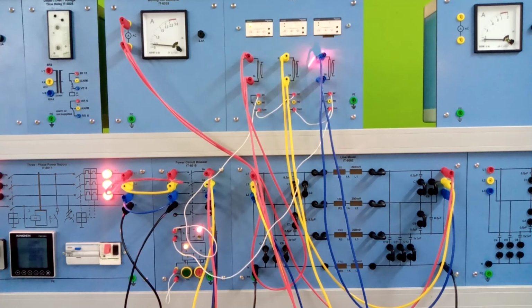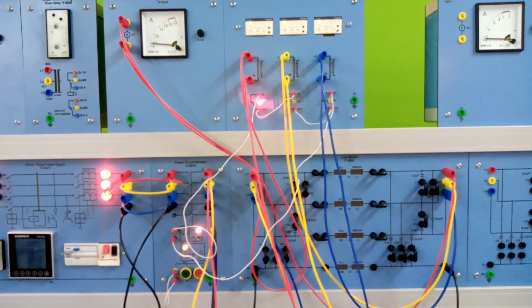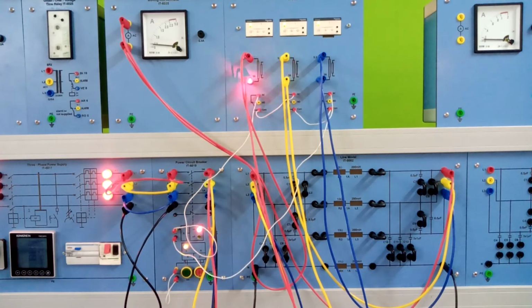We have reset them again and they are initializing, and the third portion is about short circuiting with the ground. One phase will be short circuited with the ground, and you can short circuit either of the phases, the red one, the yellow one, or the blue one. By short circuiting any phase, this relay will trip. I will short circuit the blue phase for this instance, so I will increase the load on the blue phase.